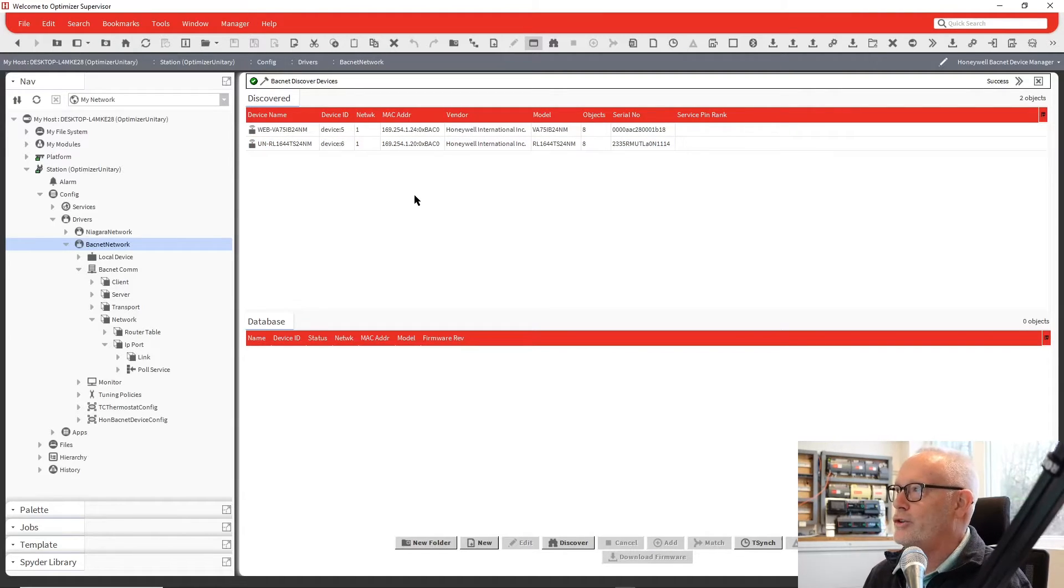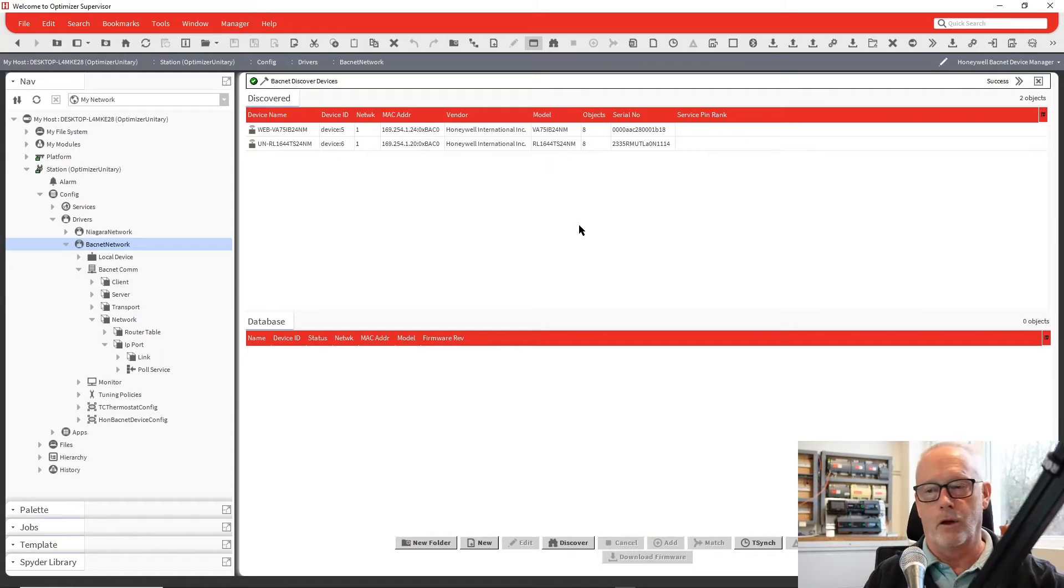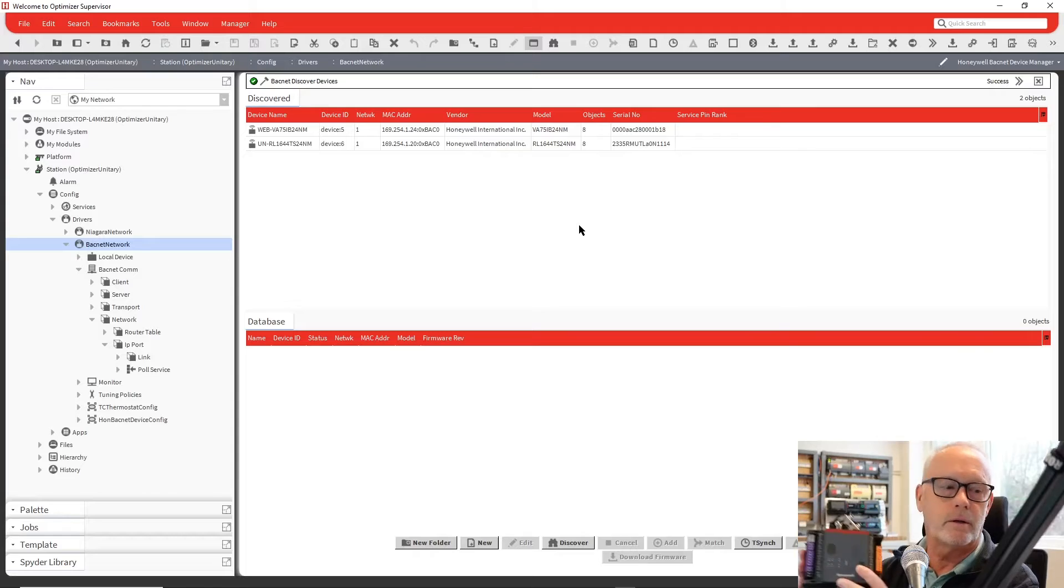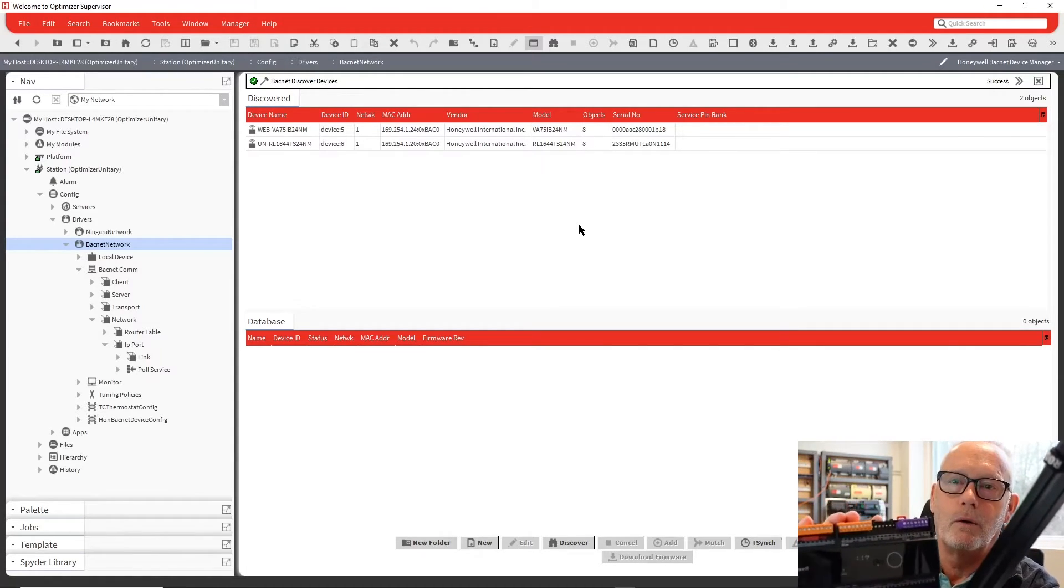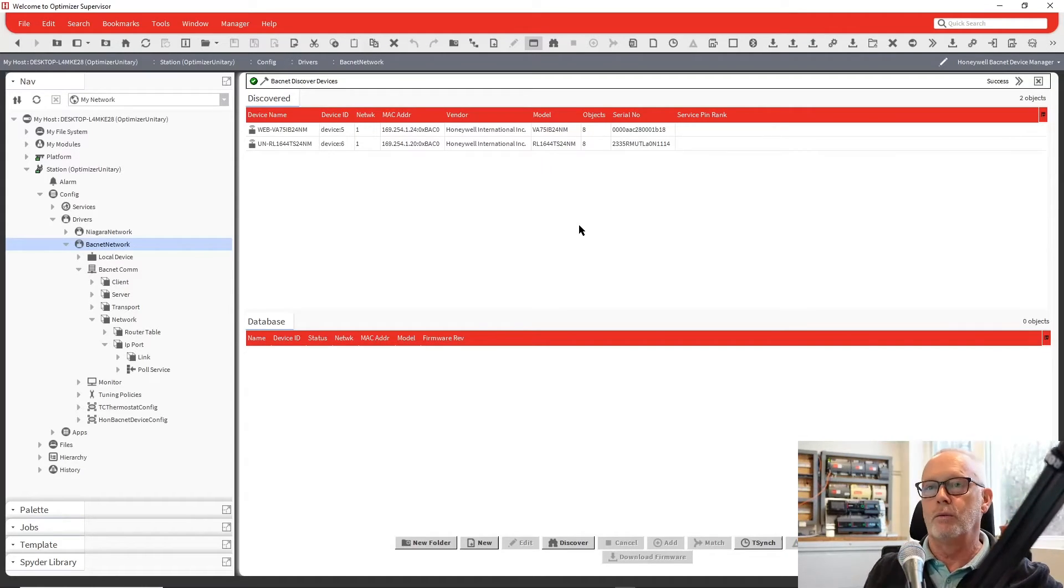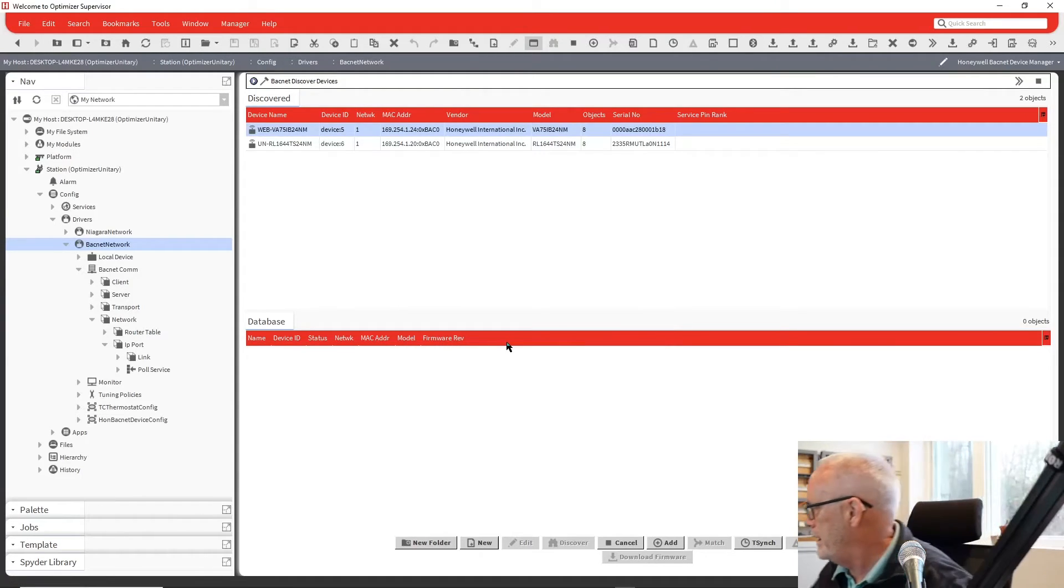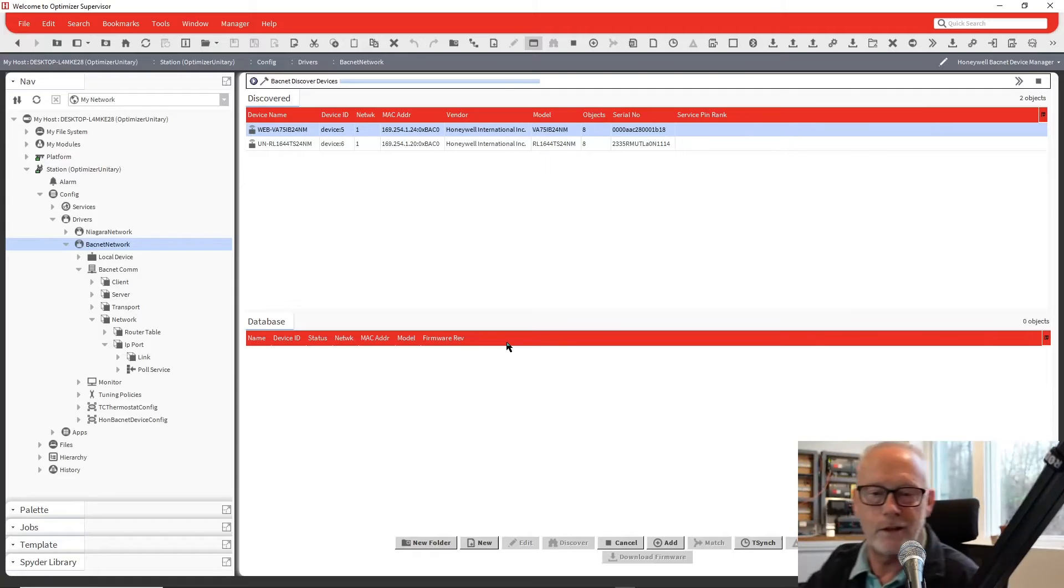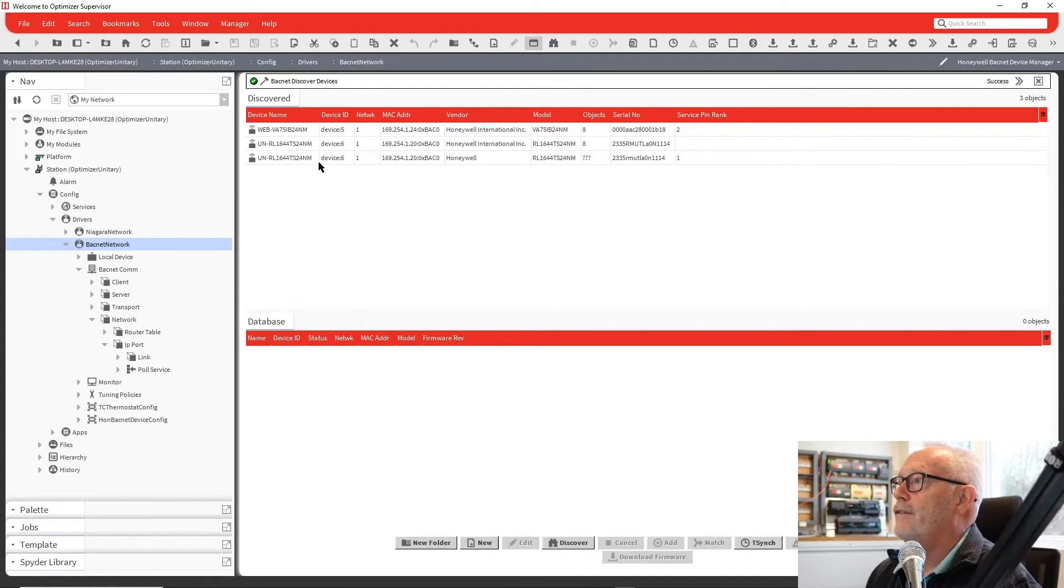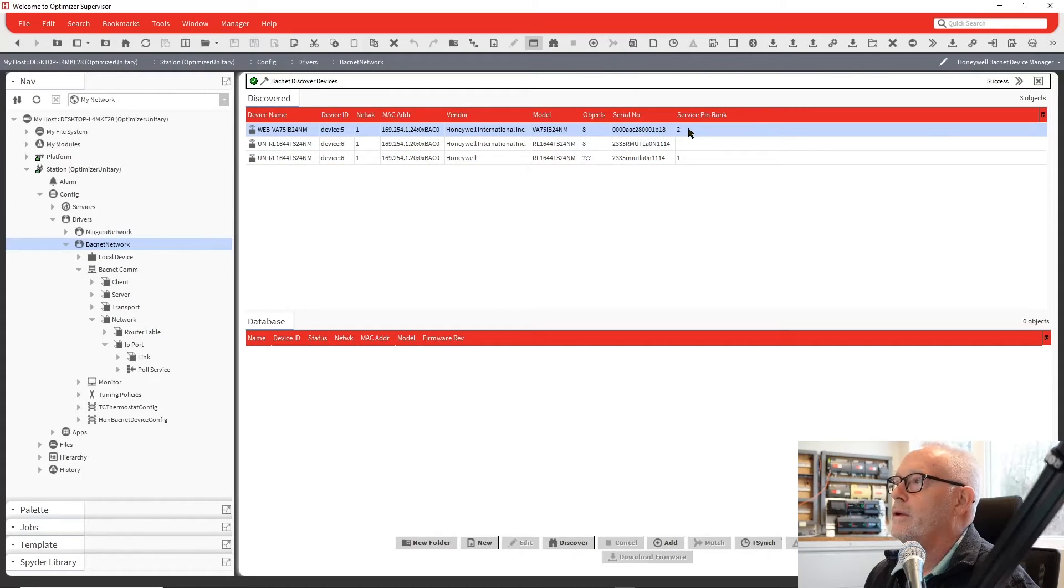Another thing, if you have a bunch of controllers you're trying to work with, and these come up but you don't know which one's which, there's a service pin ranking that's available. And on the controllers, there is a service pin or a service button. You'll see on the VAV one, it's a round circle, a round button. You can press that. And over on the unitary controller, we have the button on there as well. So what we would do is when you go in to do your discover, I'll say go ahead, discover. And I'm going to hit the buttons. I'm going to hit my unitary first, and I'm going to hit then the VAV controller. And then when it's finished, it should show the order of me pressing the button.